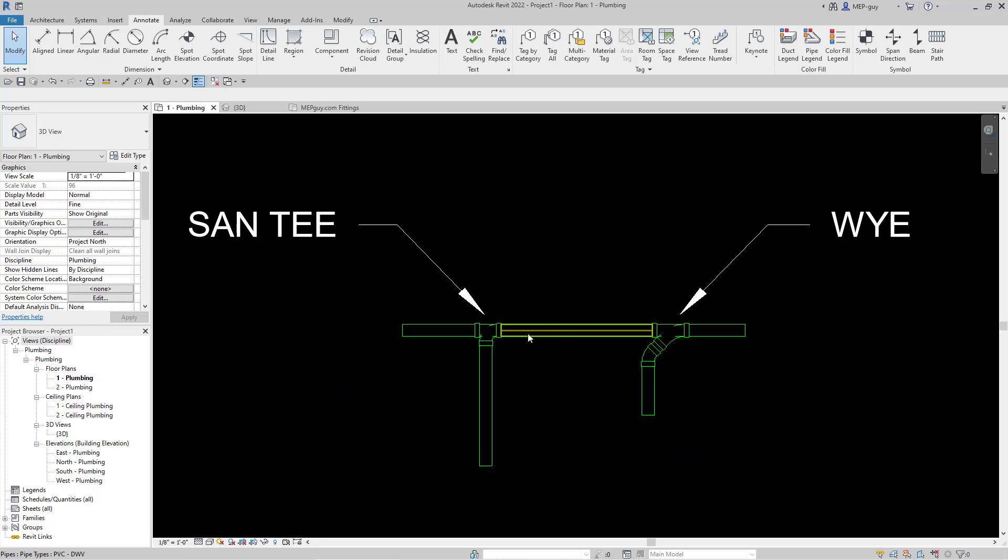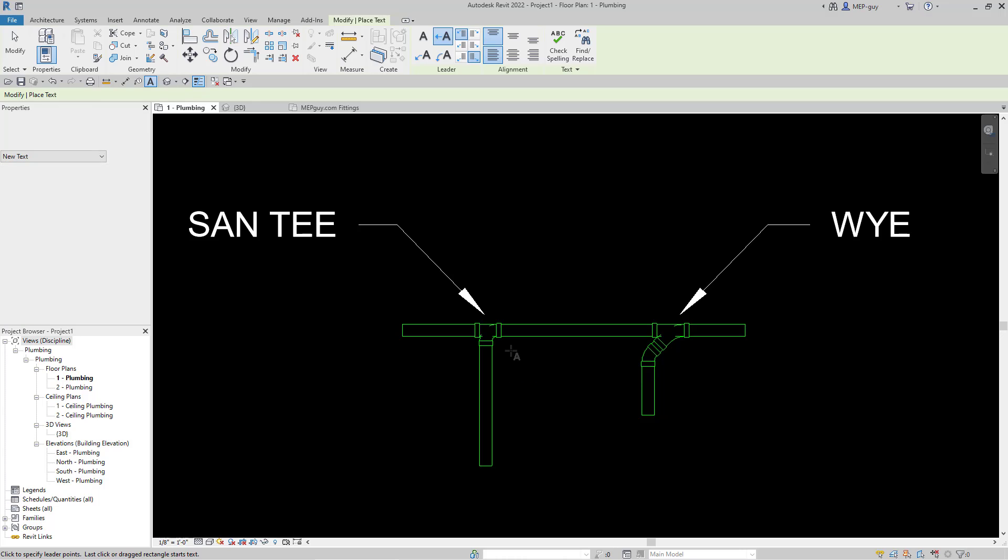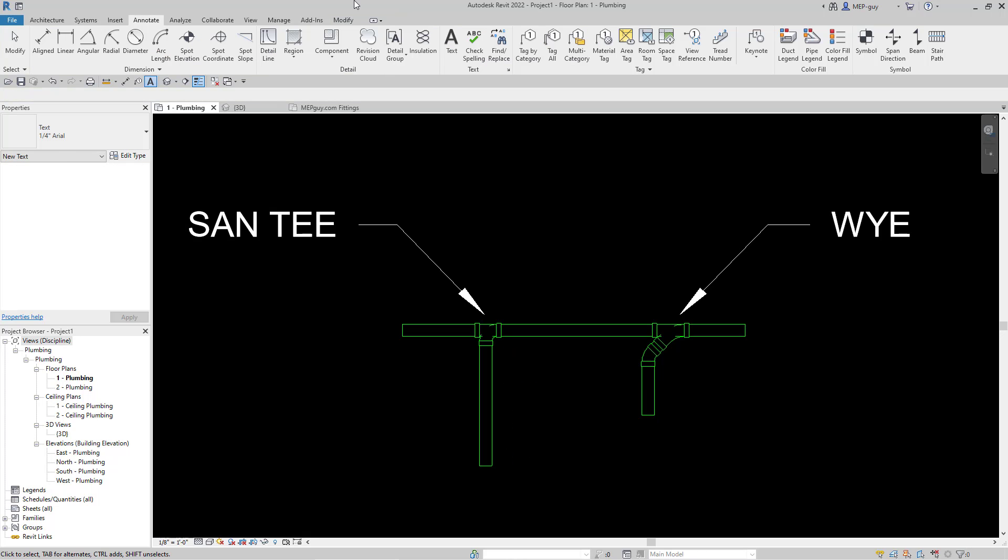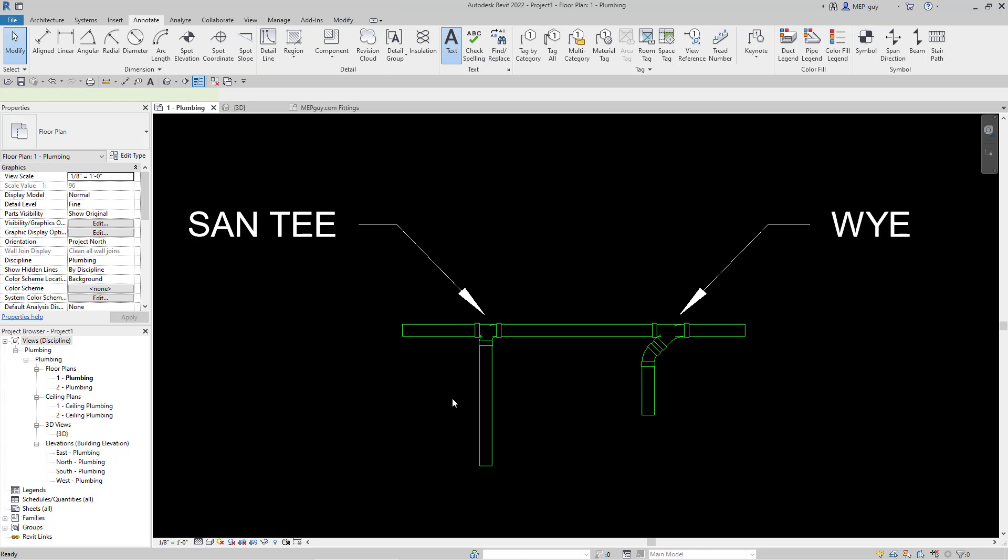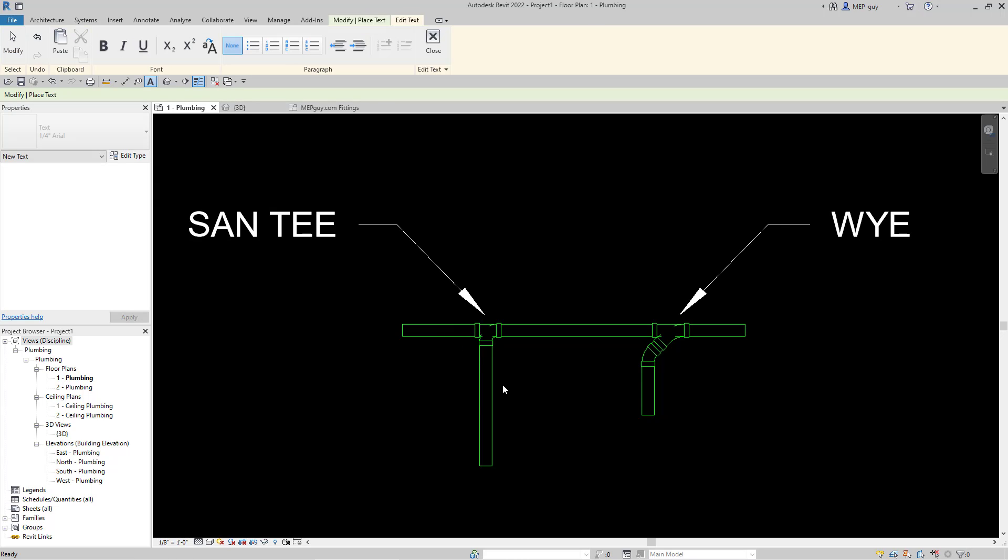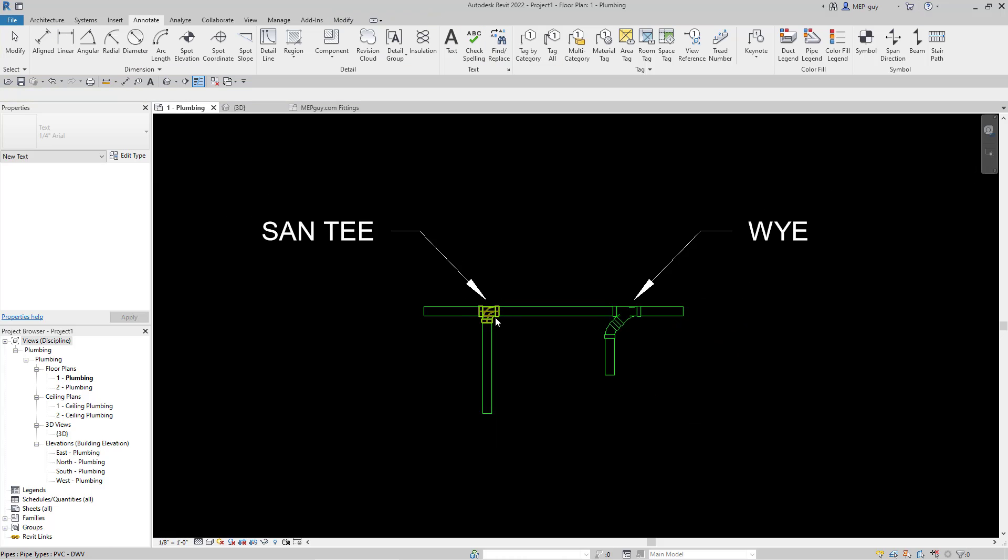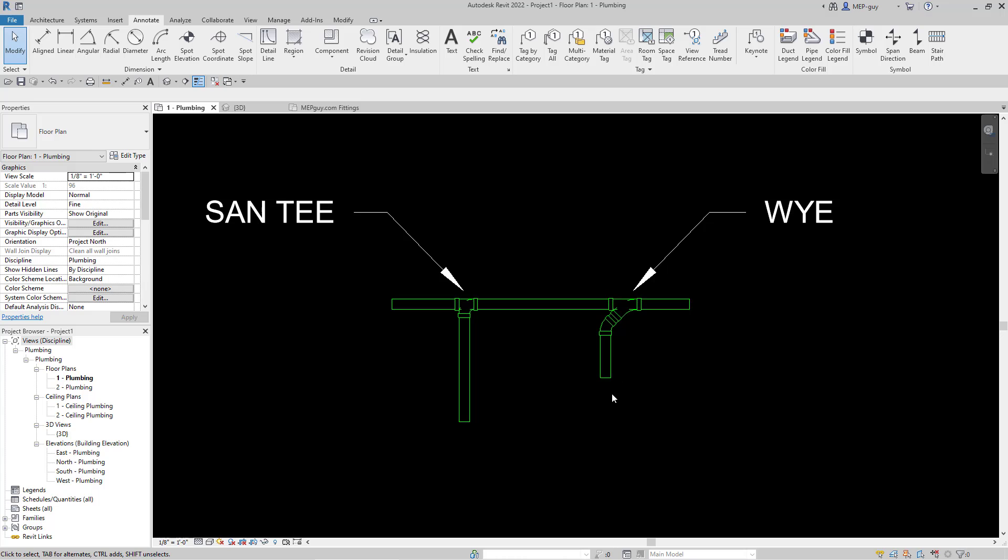So let's go back to our floor plan. And what I mean by smooth transitions, so if we had sanitary drainage flowing this way, and we also had sanitary drainage flowing this way, you can see that when they would come together, it's more likely that a clog is going to occur when you're just using this tee fitting as opposed to using this nice smooth transitional Y fitting.